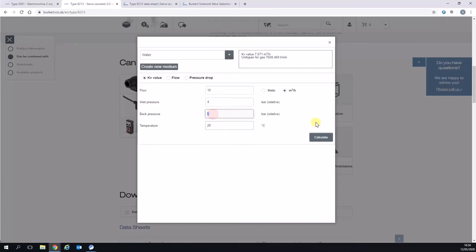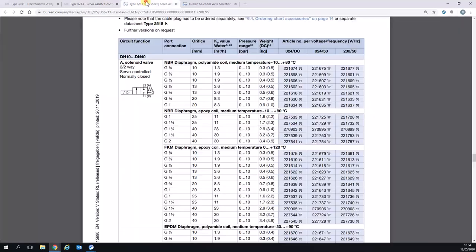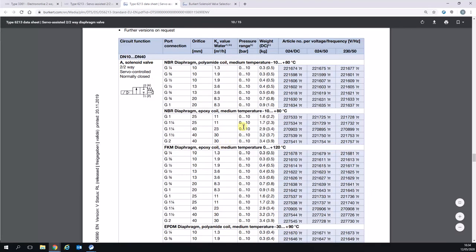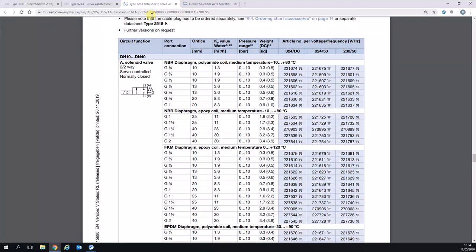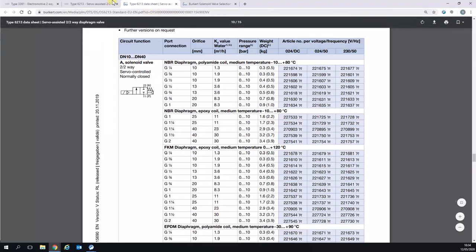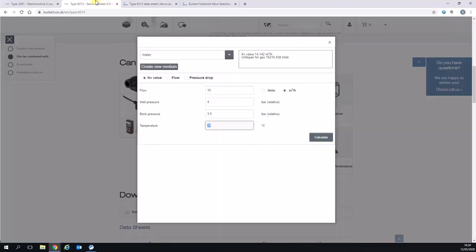What if we go back in the other direction and we only give it half a bar pressure drop? You'll notice that the KV value now is 14. So when we go back to our data sheet to achieve a KV of 14, we actually need to increase the line size and orifice size to G one and a quarter 40 millimeter orifice because that has a KV of 23. So the valve would be more expensive because we've only got a small potential pressure drop available.